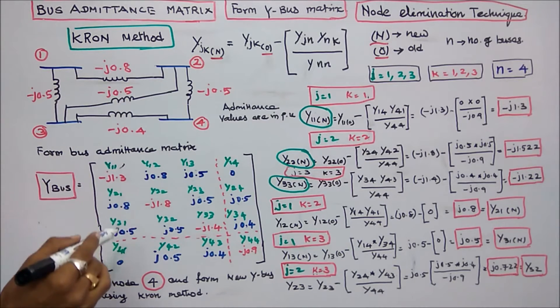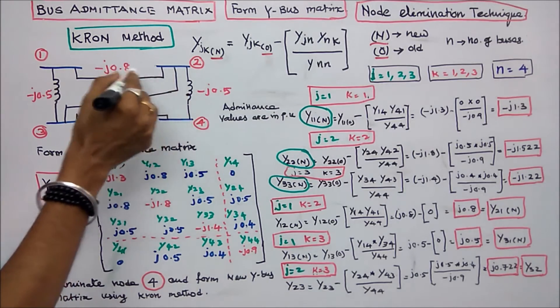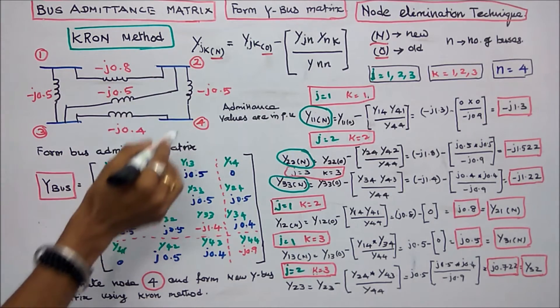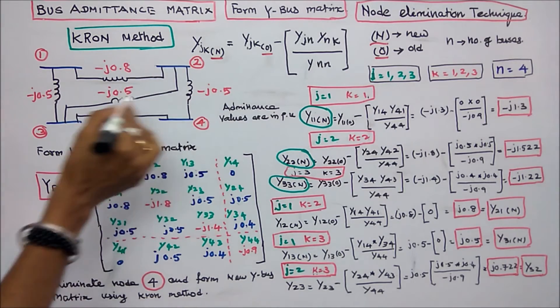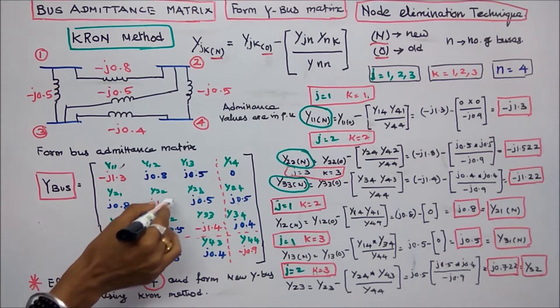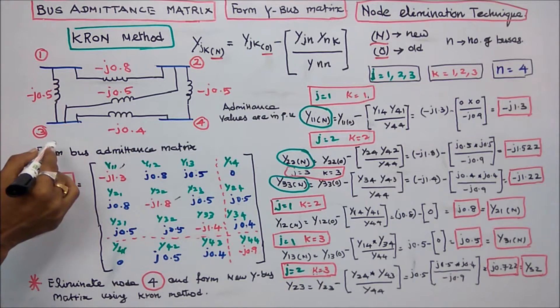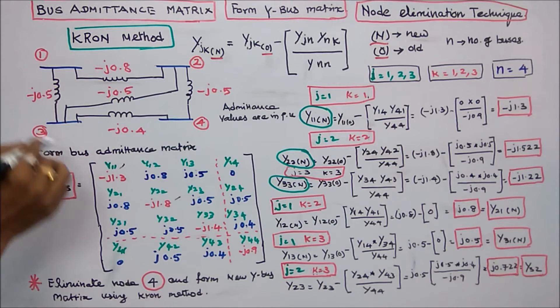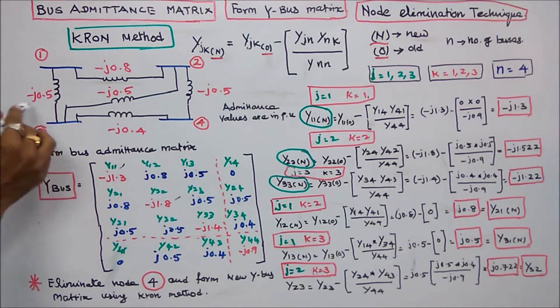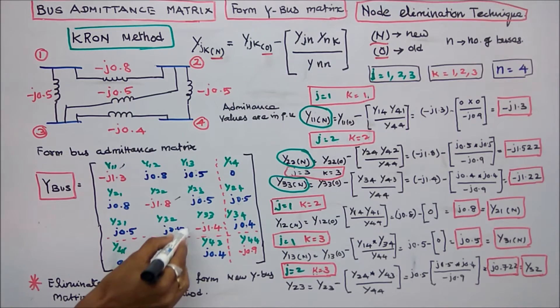The next diagonal element is Y22. Three lines are connected to bus 2: minus j0.5, minus j0.5, minus j0.8, giving Y22 equal to minus j1.8. For Y33, three lines are connected: minus j0.5, minus j0.5, minus j0.4, giving Y33 equal to minus j1.4.